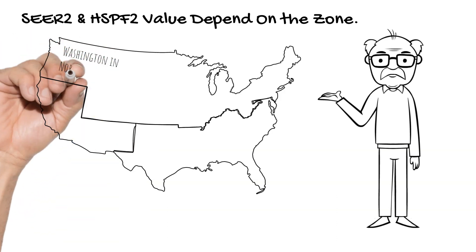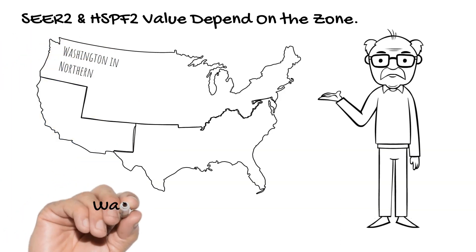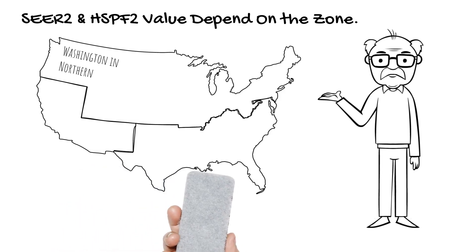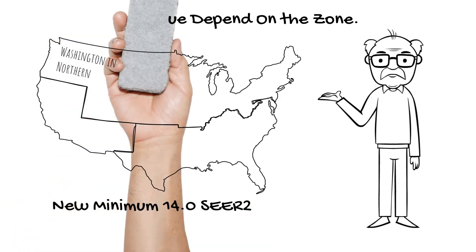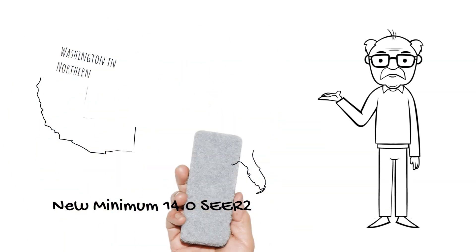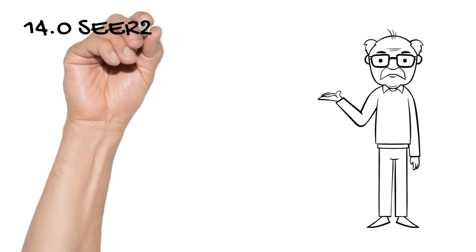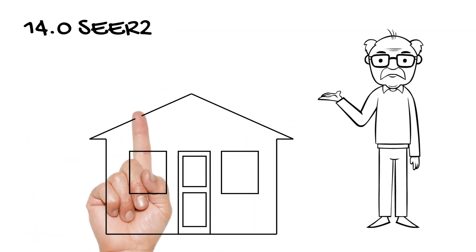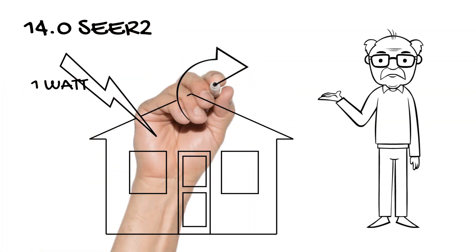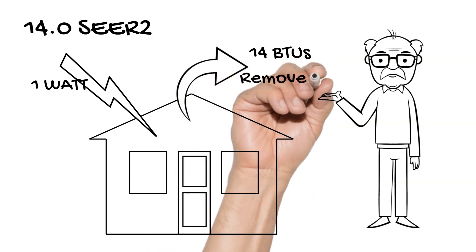Here in Washington, the previous minimum was 13.0 SEER. The new minimum is 14.0 SEER2. 14.0 SEER2 means that for every watt of power used to cool your home, 14.0 BTUs must be removed.